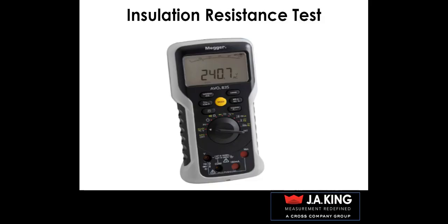This test requires a mega ohm meter. Caution: never use a voltage higher than 50 volts DC to measure insulation resistance on load cells. An insulation resistance test is carried out when there are unstable readings and/or random changes in the zero balance point of the load cell. It measures the resistance between the load cell body and all its connected wires as follows.